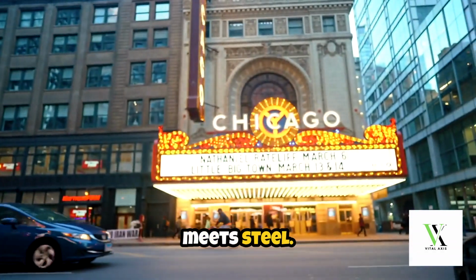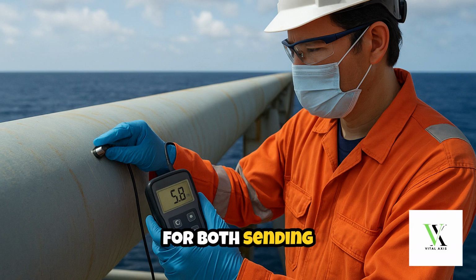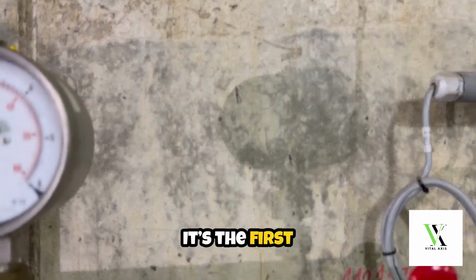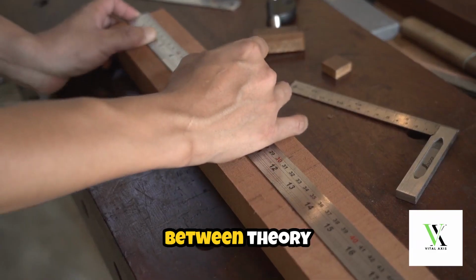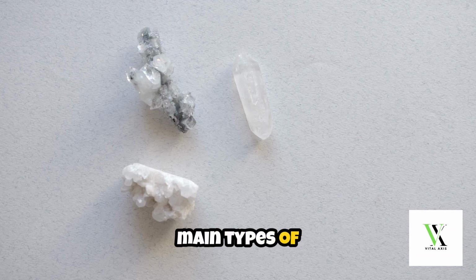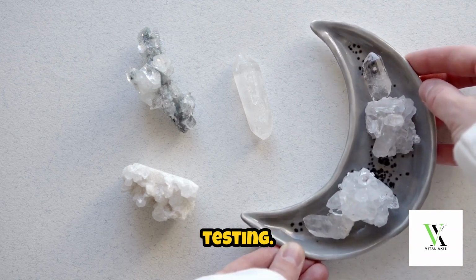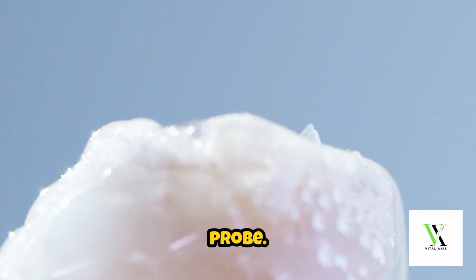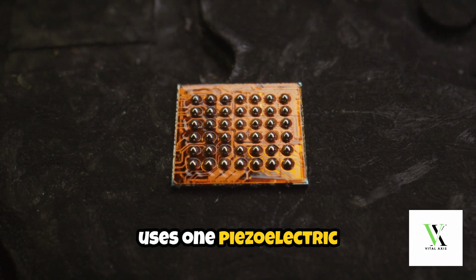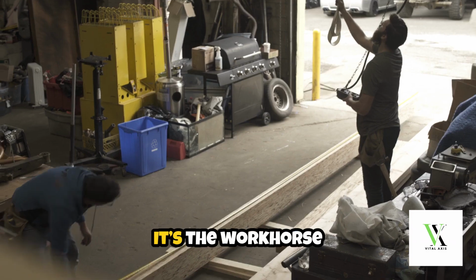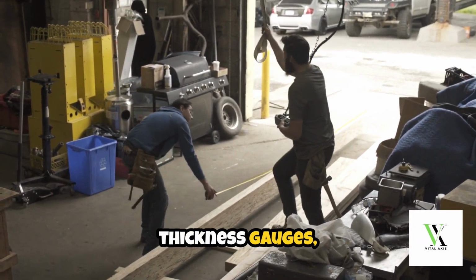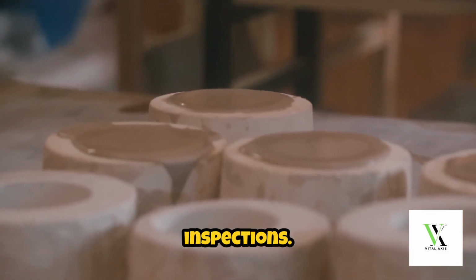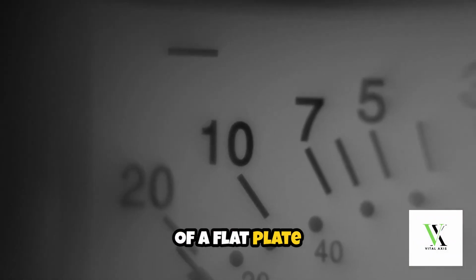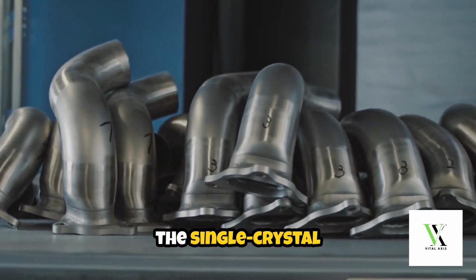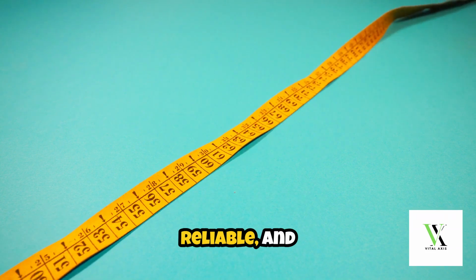The probe, sometimes called the transducer, is where science meets steel. This device is responsible for both sending and receiving ultrasonic signals. It's the first point of contact, the sensor that bridges the gap between theory and reality. There are two main types of probes you'll encounter in ultrasonic thickness testing. First, the single crystal or single element probe. This probe uses one piezoelectric crystal to generate and detect sound waves. It's the workhorse of straight beam thickness gauges, the tool you'll see in most routine inspections. If you're measuring the wall thickness of a flat plate or a slightly curved pipe, the single crystal probe is your go-to. Simple, reliable, and repeatable.